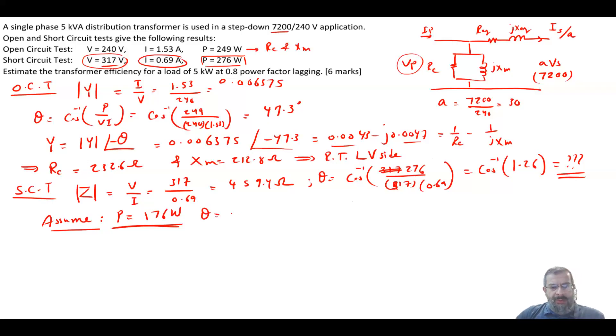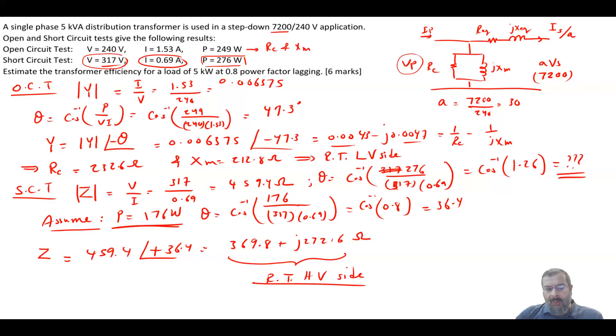So now theta will be equal to cosine inverse of 176 over 317 times 0.69, which is equal to 36.4. So your Z is equal to 459.4 angle of plus 36.4, which is equal to 369.8 plus J272.6 ohms. And this basically is referred to the high voltage side. Now, I decided to use the model referred to the high voltage side. So I will use these values as the R, but I will change the RC and XM by multiplying by A square.